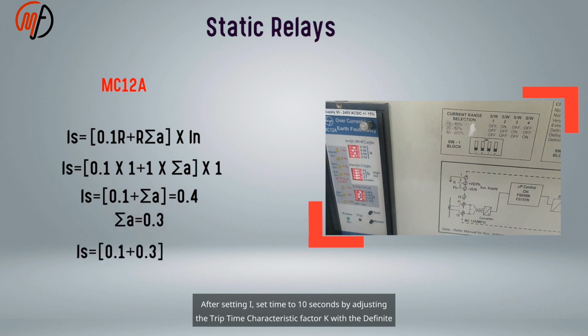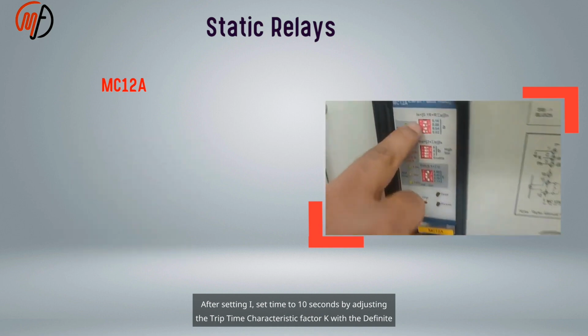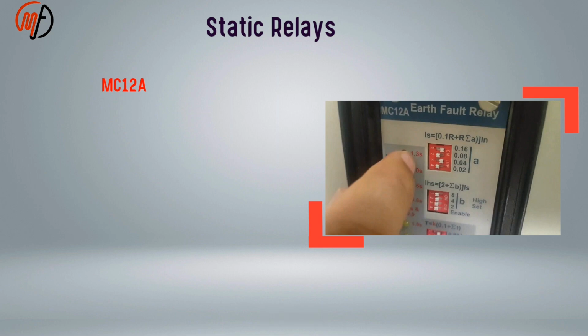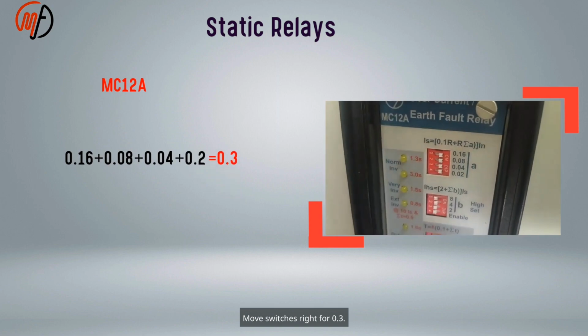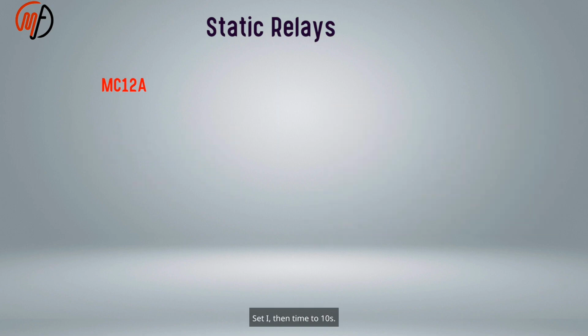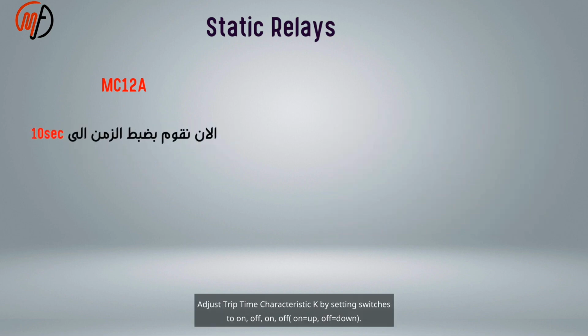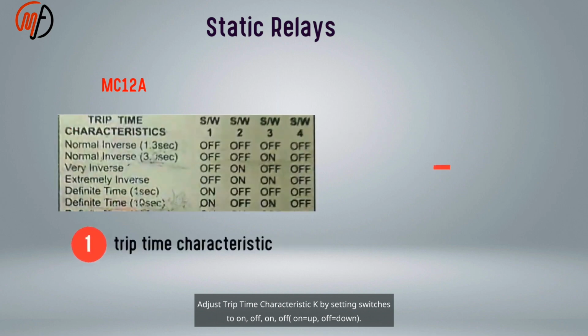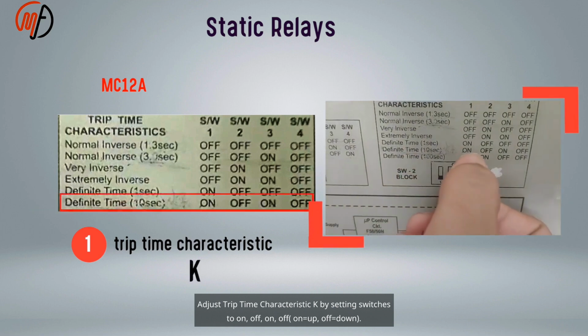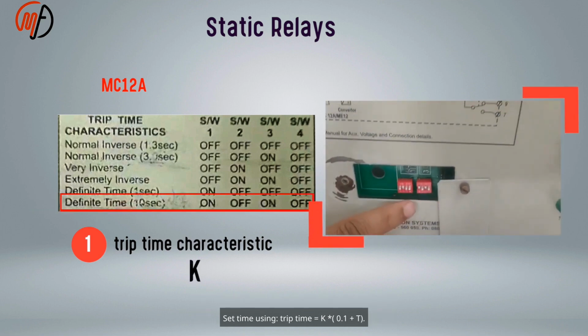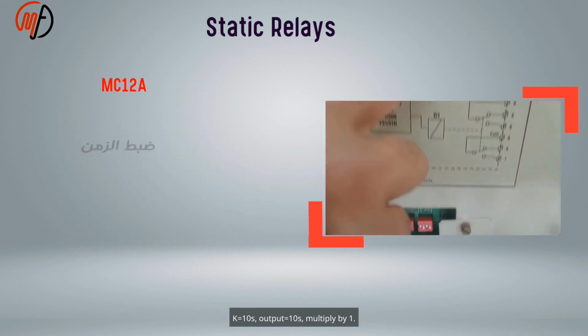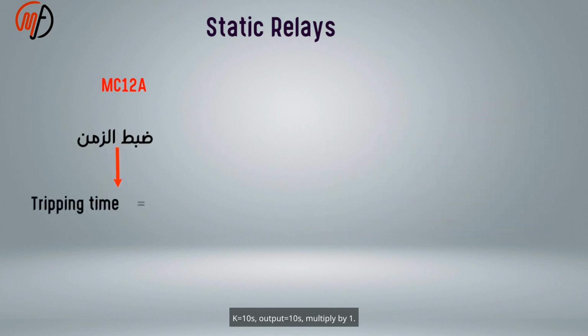After setting I, set the time to 10 seconds by adjusting the trip time characteristic factor K with the definite time switches. Move switches right for 0.3, set I, then set the time to 10. Adjust trip time characteristic K by setting switches on, off, on, off: on is up, off is down. Set time using trip time = K times (0.1 plus T). K equals 10, output equals 10, multiply by 1, T = 0.9, which is 0.1 plus 0.8.